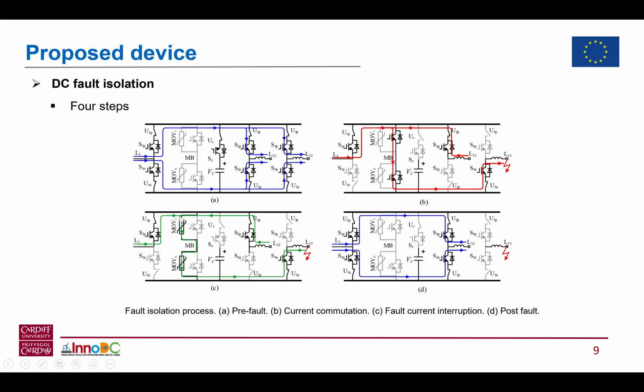The DC fault current will be reduced quickly by the MOVs. Then after the DC current is interrupted, we can isolate the fault line by switching off these two devices. After that, the system can be restored and the fault is isolated. The fault line is isolated.